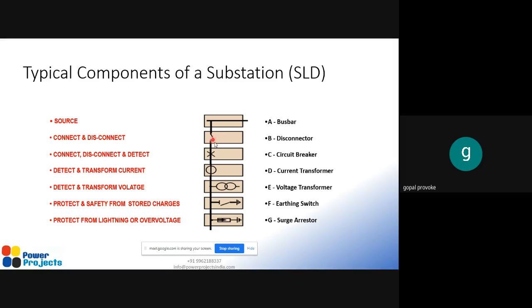From the bus bar, we have a disconnector, a circuit breaker, then a current transformer, a voltage transformer, an earthing switch, and a surge arrestor. These equipments each have their own purpose, which we will see in detail now.